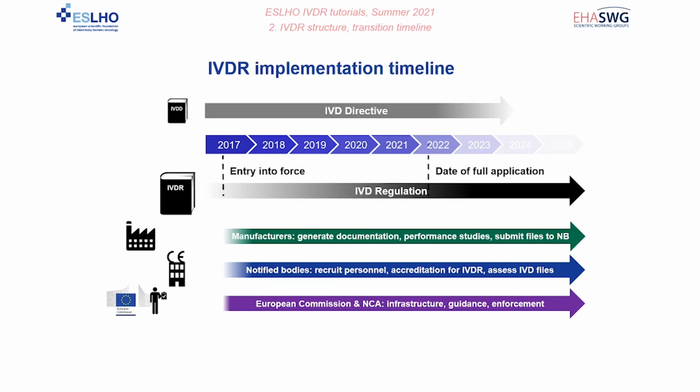Then the notified bodies. There is one IVDR requirement that has a huge impact on their work. Under the IVDD, only a small selection of high-risk devices needed to be reviewed by notified bodies, but under the IVDR, most devices will have to be reviewed by a notified body. Therefore, the workload for notified bodies will increase substantially.